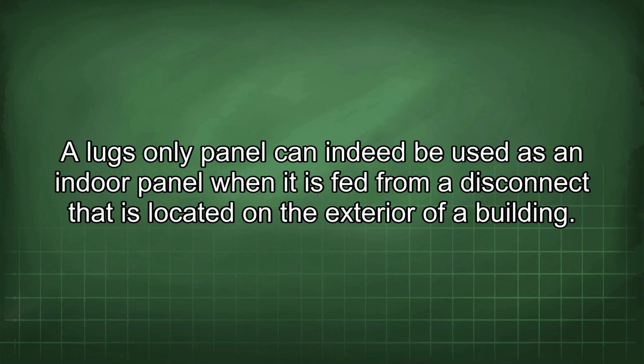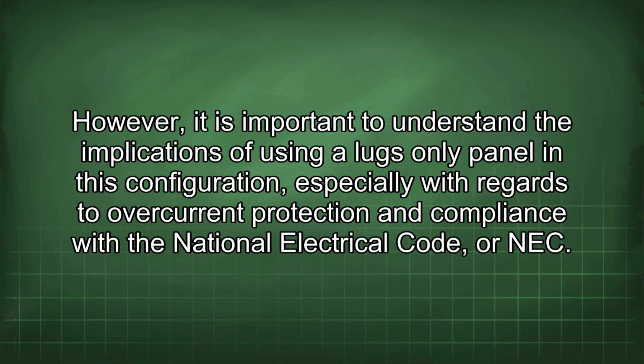A lugs-only panel can indeed be used as an indoor panel when it is fed from a disconnect that is located on the exterior of a building. However, it is important to understand the implications of using a lugs-only panel in this configuration, especially with regards to overcurrent protection and compliance with the National Electrical Code, or NEC.